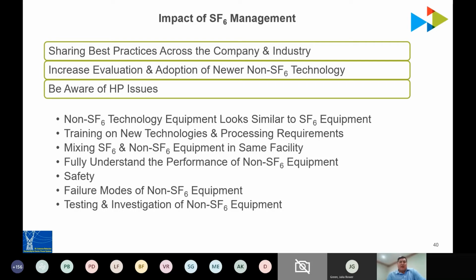We're also looking at evaluation and adoption of newer non-SF6 technology a little faster than we have in the past, to mirror what Julia was sharing with our environmental focus. One of the biggest things is we're aware of HP issues — this equipment looks the same, and it's going to be very hard for the workforce to differentiate between the equipment. We're doing things with stickers, badges, and signs to make it more robust in our system, so we don't get confused about whether it's a gas breaker, a clean air vacuum, or something else.